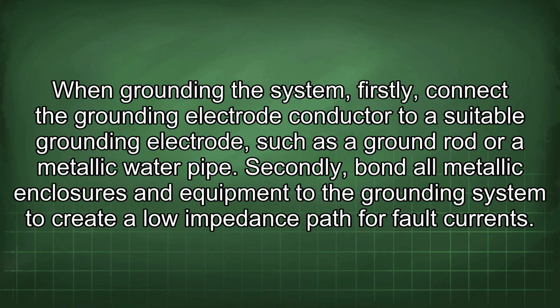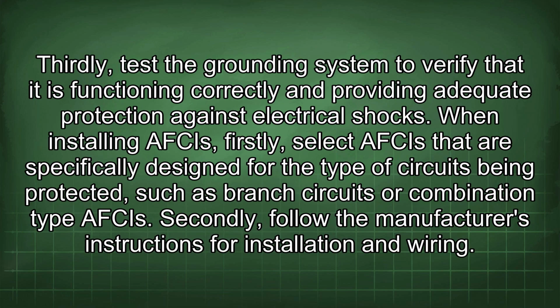When grounding the system, firstly, connect the grounding electrode conductor to a suitable grounding electrode, such as a ground rod or a metallic water pipe. Secondly, bond all metallic enclosures and equipment to the grounding system to create a low impedance path for fault currents. Thirdly, test the grounding system to verify that it is functioning correctly and providing adequate protection against electrical shocks.